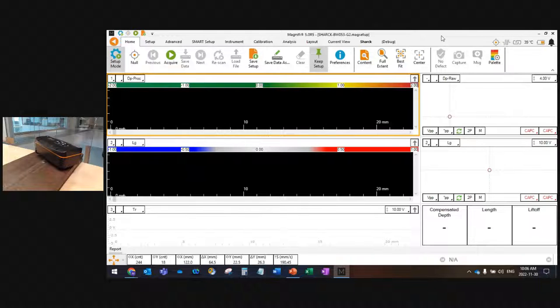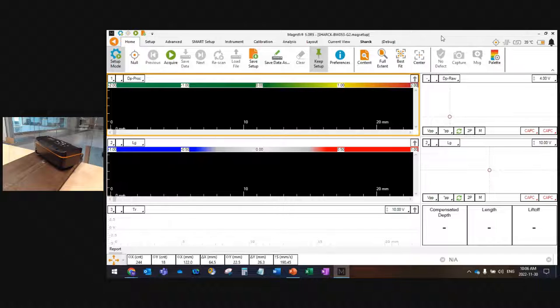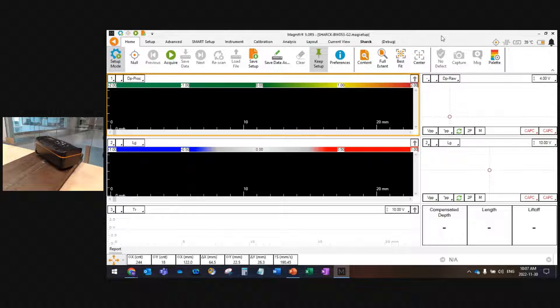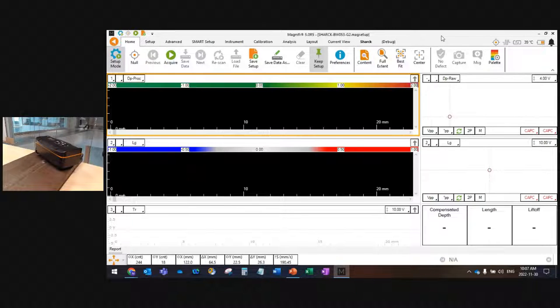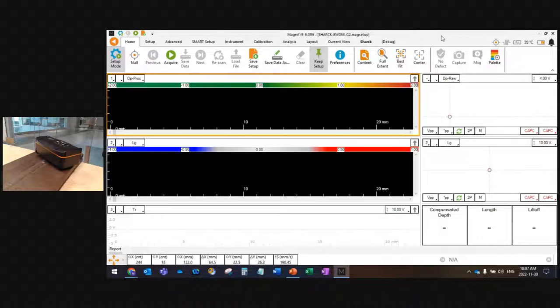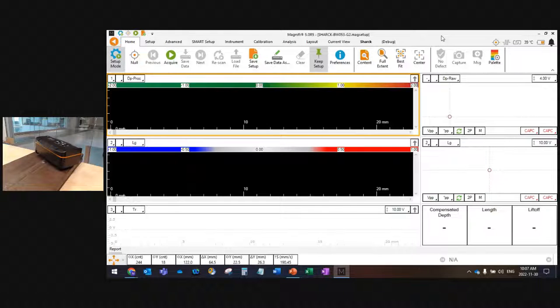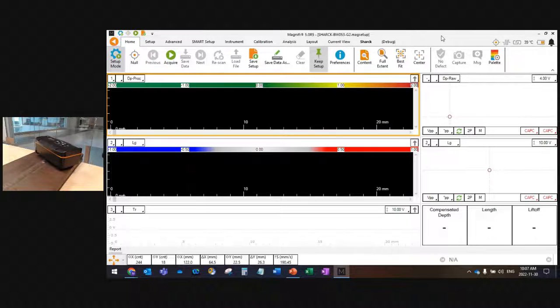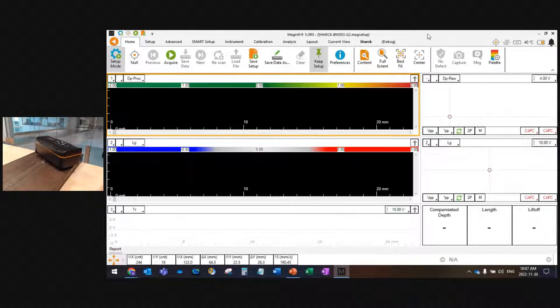What's really nice about Shark is that you don't need to build your own sizing curves. You don't need to have a reference standard with flaws of known depth. This is commonly a problem with eddy current array. But the beauty of Shark is that everything has been done by Eddyfi over eight years of development and improvements. When you load this setup in Magnifi, everything is embedded. The software knows exactly what it's doing and it will give you the depth values on all carbon steel surfaces.